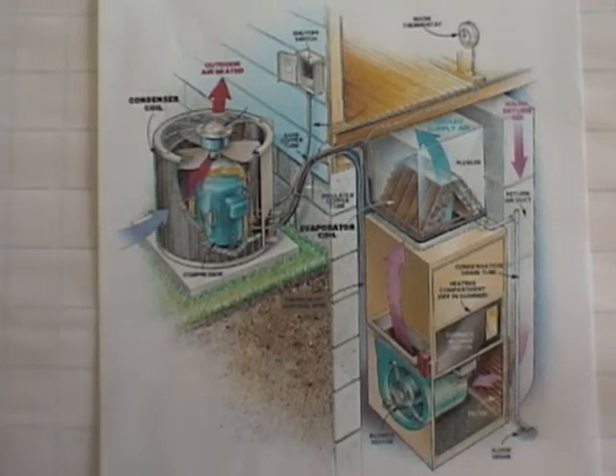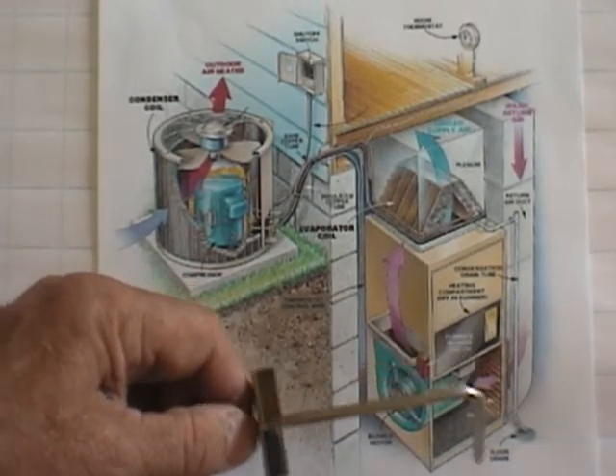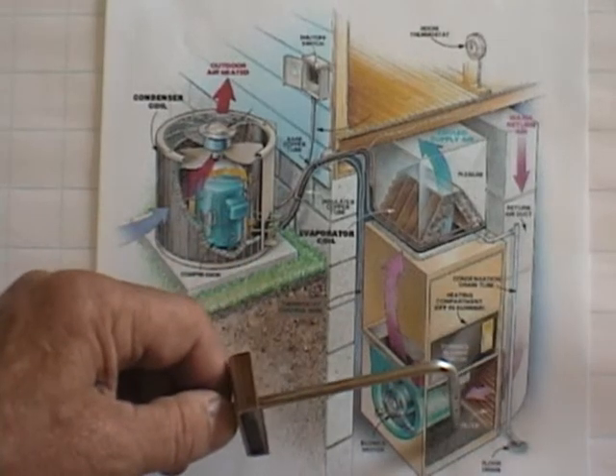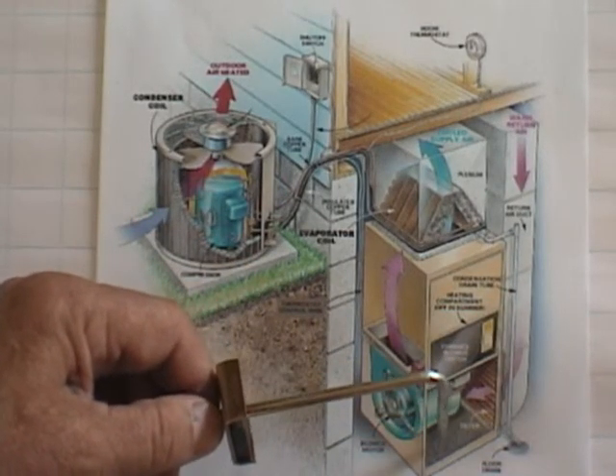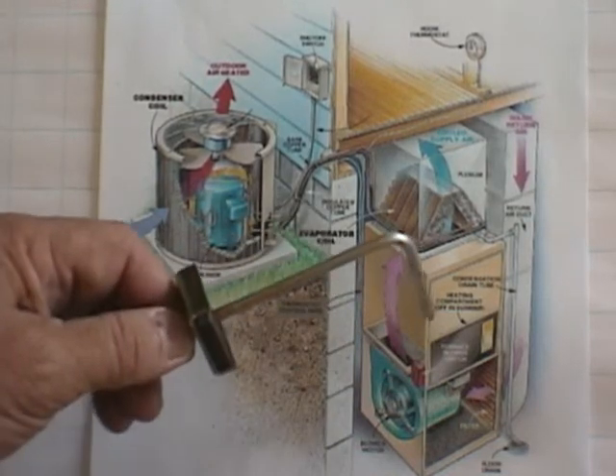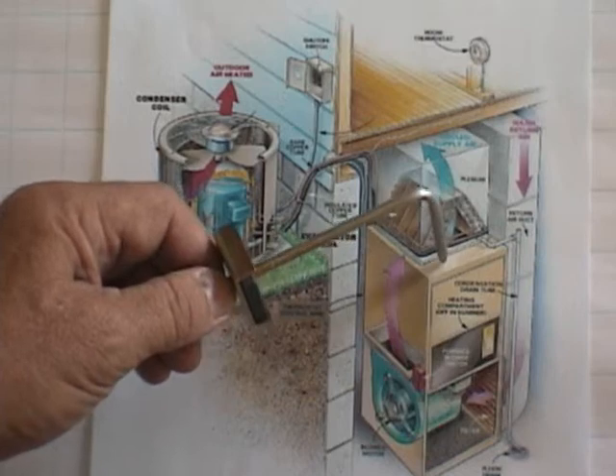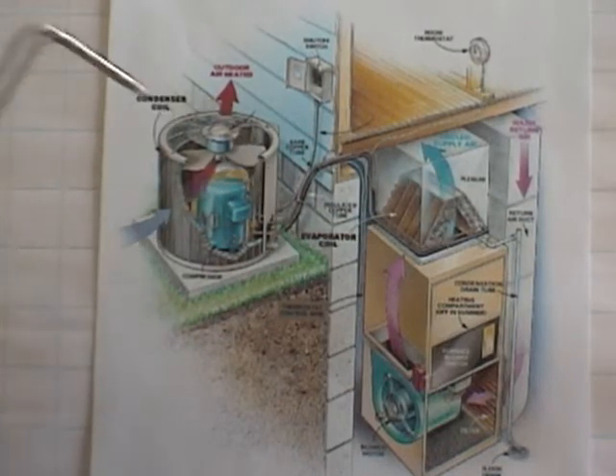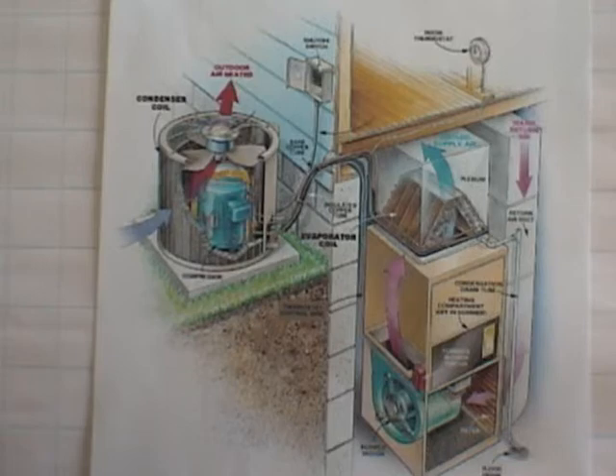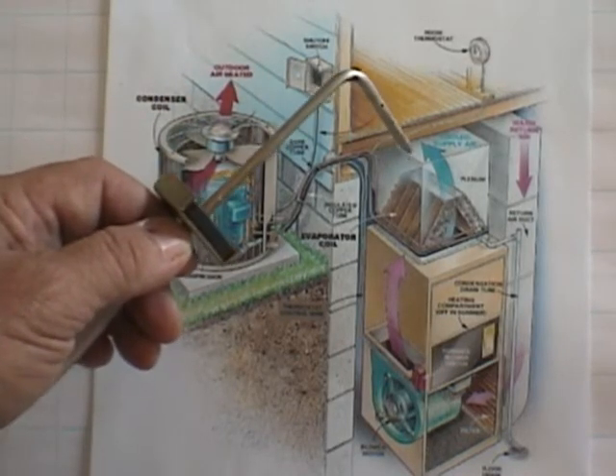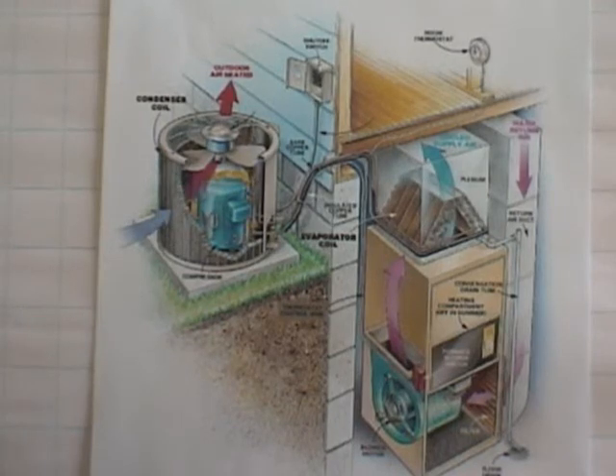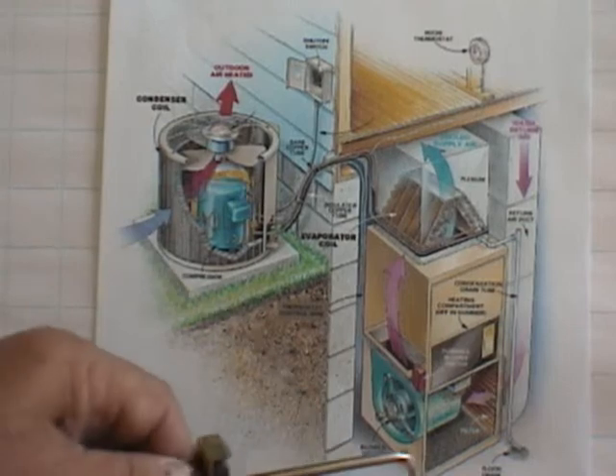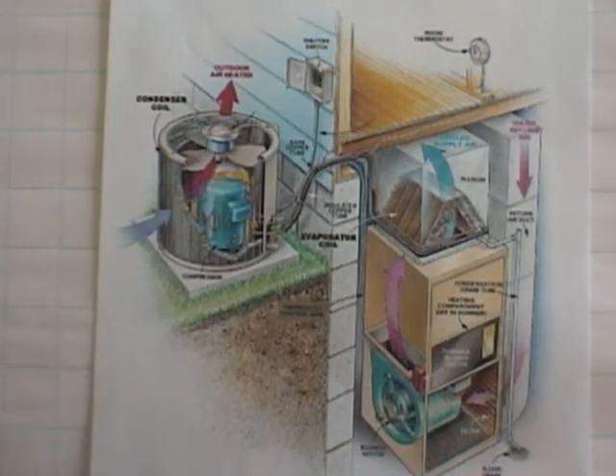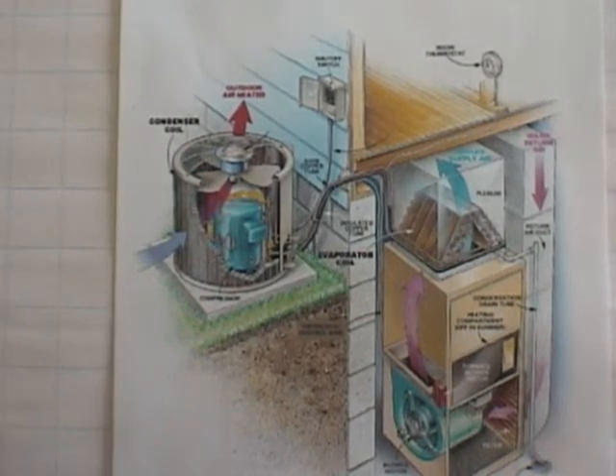But a good piece of information is, of course, pressure drop across the filter. So you could take your reading in the return air and then in the suction side, and that would tell you how much pressure drop you have for this filter. If you have a highly restrictive filter, that could be a problem. You could take your pressure drop across the coil and compare that to published data, and that would tell you whether you have a fouled or stopped up coil. If you have a high static discharge pressure, that would tell you that you have a restrictive duct system. If you have a high suction negative pressure from the fan inlet, then that would tell you you have a restrictive filter, restrictive return system, restricted return air grill, that kind of thing.